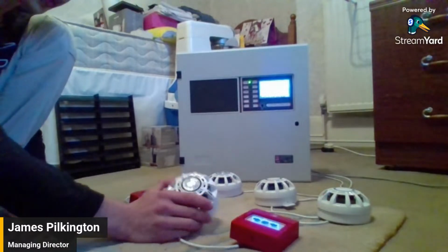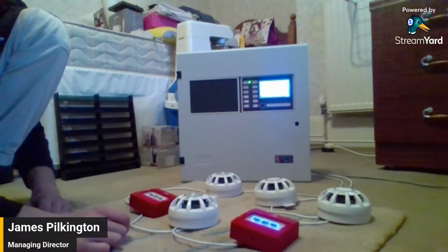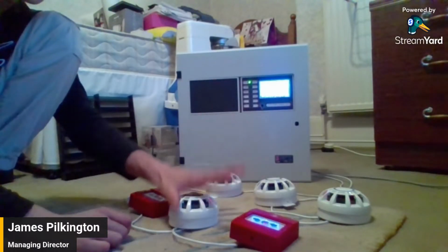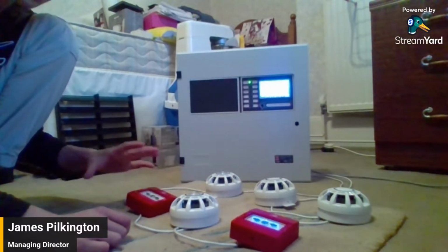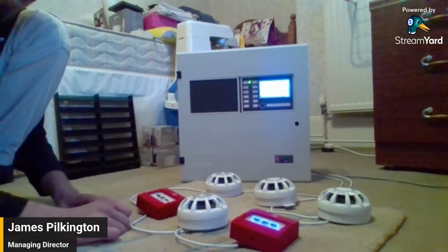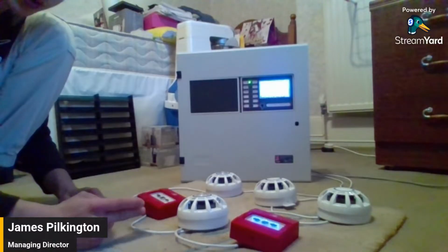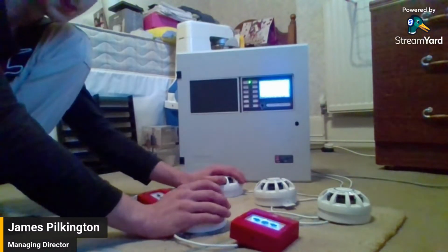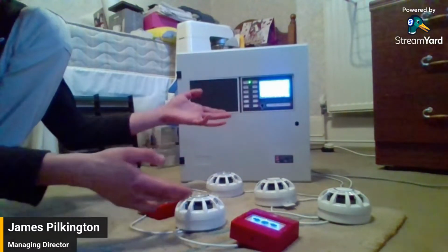That's just one interesting feature built in with Cast Pro, but there are a lot of other interesting features that Cast Pro does hold. Again, you've got 32 tone sounders built into these detectors, so you've got compatibility with many different countries and environments where these systems could be used. So if you've got an environment where the normal fire alarm tone could clash with equipment, you can set the tones on these sounders to something different.